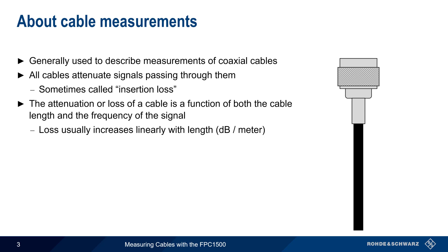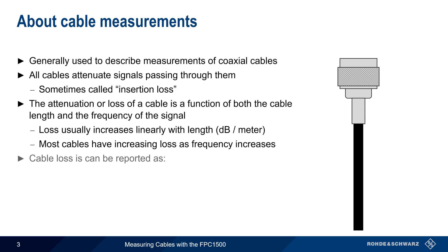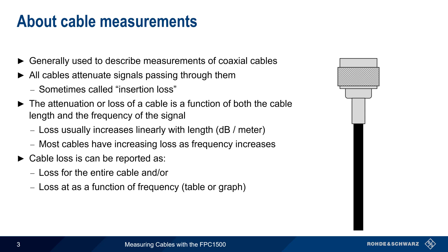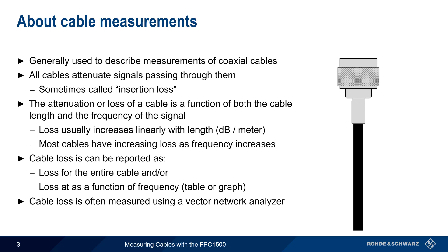Loss can therefore be expressed in units of dB per meter or foot. But more importantly, most cables also have increasing loss as the frequency increases. Cable loss can therefore be reported as a single value in dB for the entire measured cable, and it can also be given as the amount of attenuation or loss as a function of frequency, in either tabular or graphical format. Although there are many ways of measuring cables, the most common and the most accurate is using an instrument called a Vector Network Analyzer, or VNA.